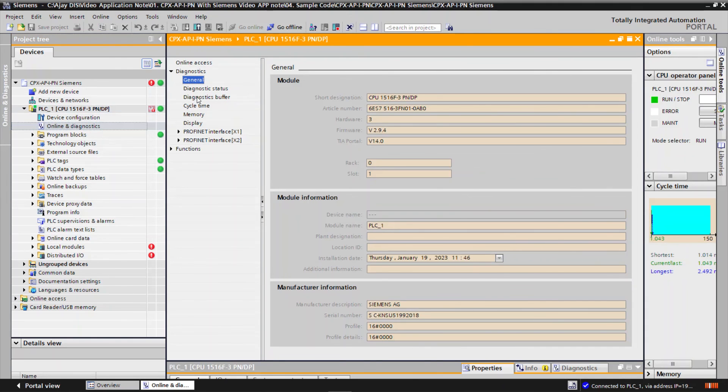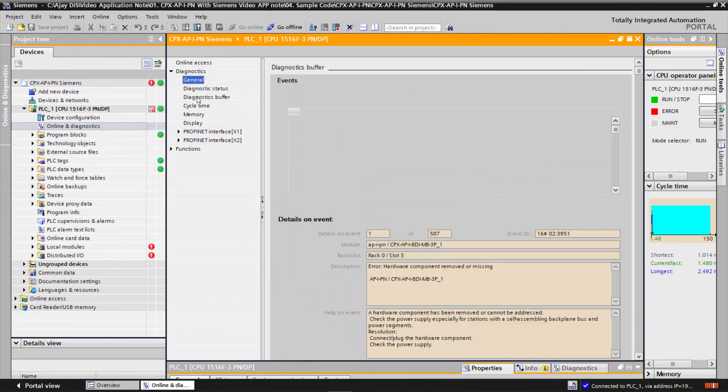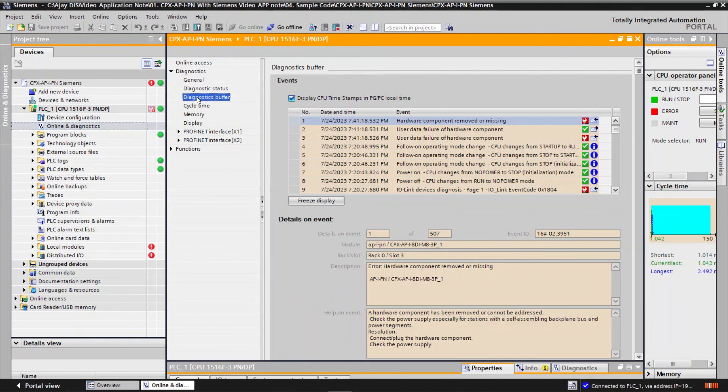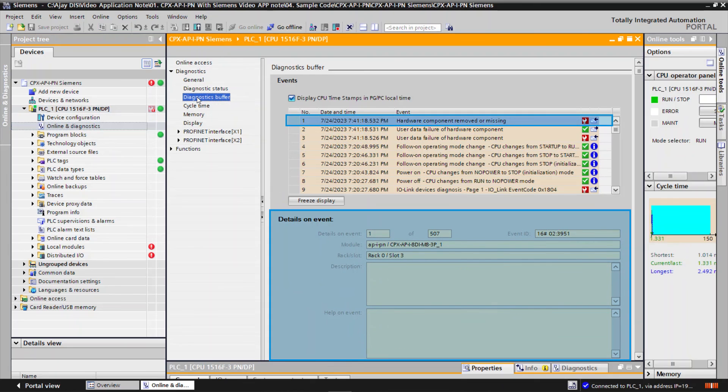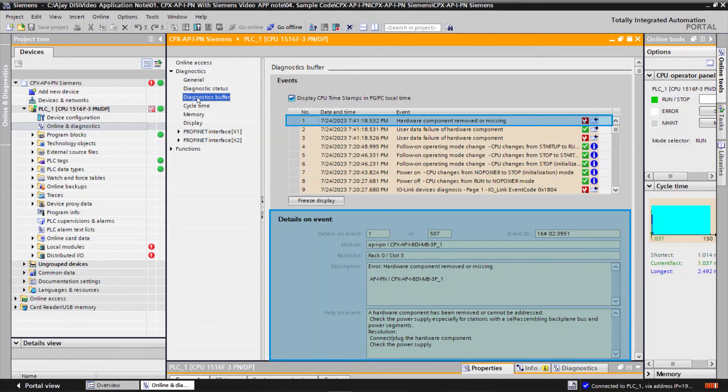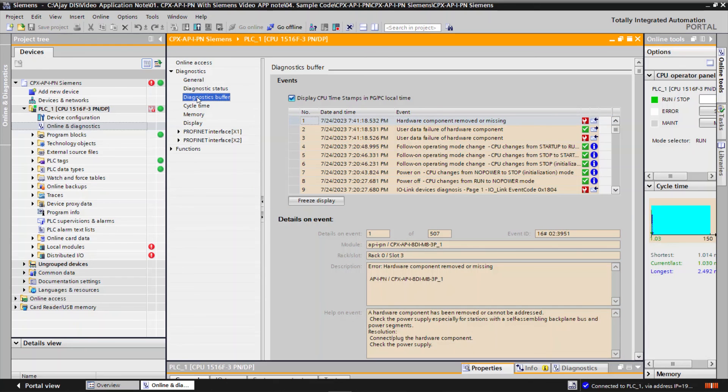Go to Diagnostics buffer. Diagnostics information like name of the error occurred module, error description, and some remedies to clear the error will be seen. In this example we have interrupted AP communication 8 DI module.